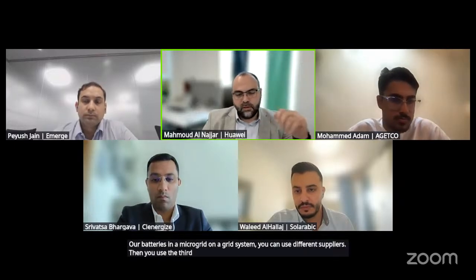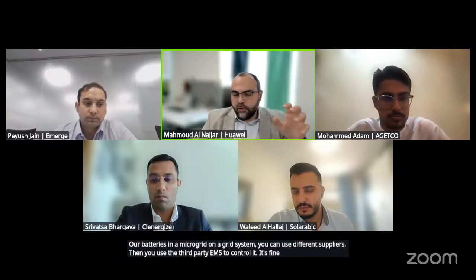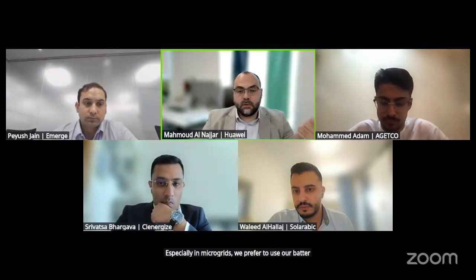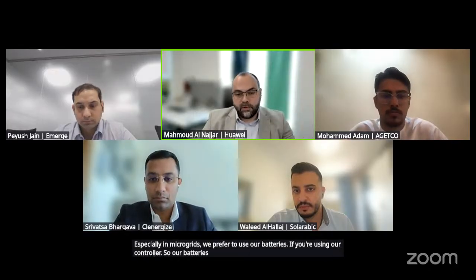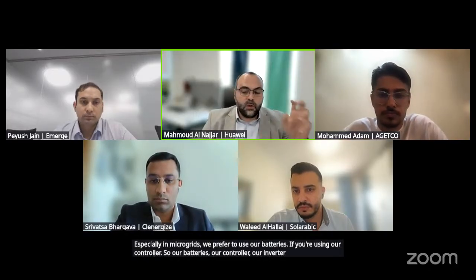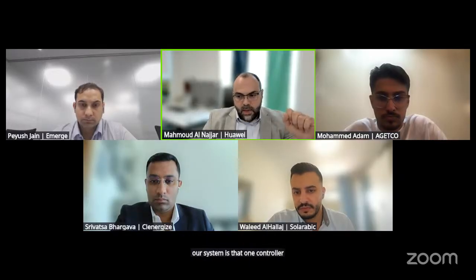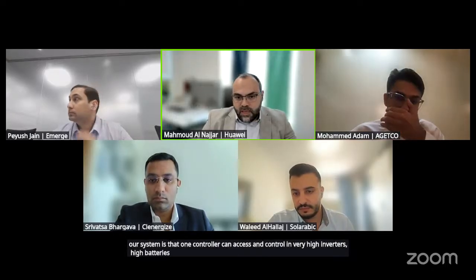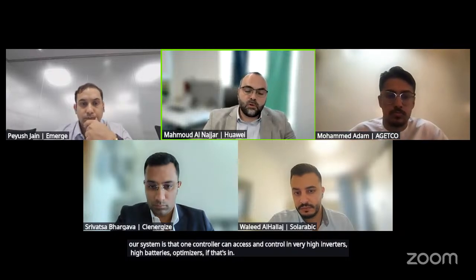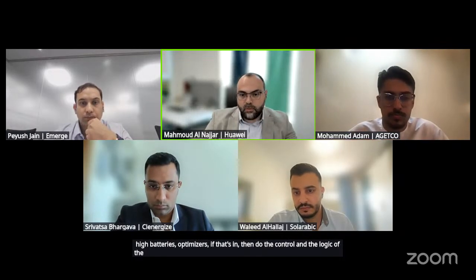Our batteries, in a microgrid or on a grid system, you can use different suppliers. Then you use a third-party EMS to control it. It's fine. Especially in microgrids, we prefer to use our batteries if you're using our controller. So our batteries, our controller, our inverter. So we unify the communication language. This is one of the advantages of using the Huawei system: one controller can access and control Huawei inverters, Huawei batteries, and optimizers if they're in, and then do the control and the logic of the full microgrid or the off-grid operation.